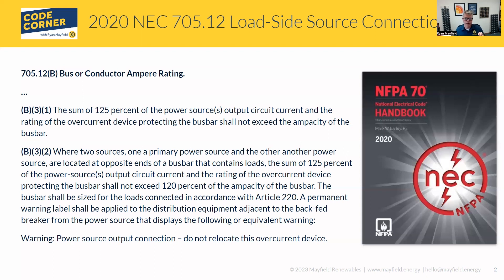If you take 125% of the output current — so 32 amps times 1.25 is 40 — if that 40 amps plus the overcurrent protection for that bus bar, the sum of those doesn't exceed 120% of the bus bar rating, you can make that connection. But you have to put the new solar connection at the opposite end of where the utility connection is coming in. So in a top-fed panel, you'd have 200 amps coming in from the top for the utility, and the 40-amp source for the PV system would go at the bottom.